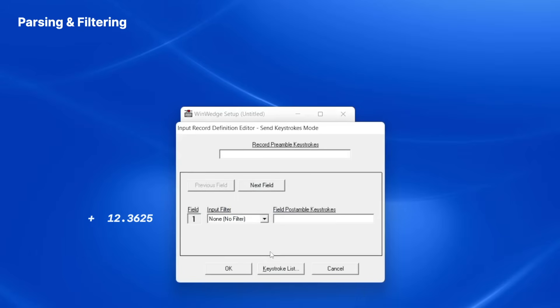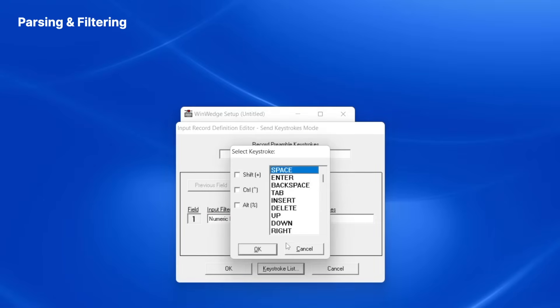My first field contains the weight value. I'll set the filter option for field 1 to numeric data only to make sure that only the number is sent to Excel. After WinWedge types the first field in a cell, I want the cursor to tab automatically to the next cell. So I'll select the Field Postamble Keystrokes text box and click Keystroke List. I choose the tab keystroke from the list and click OK.